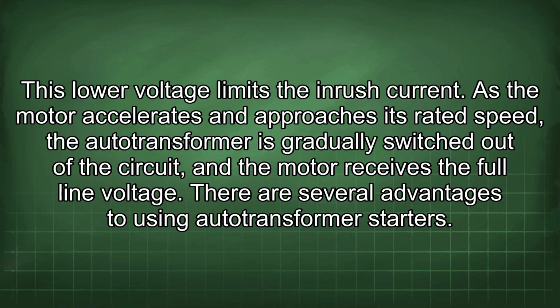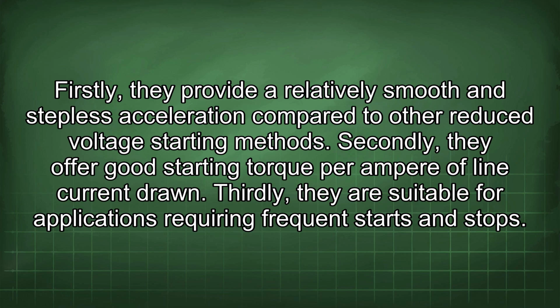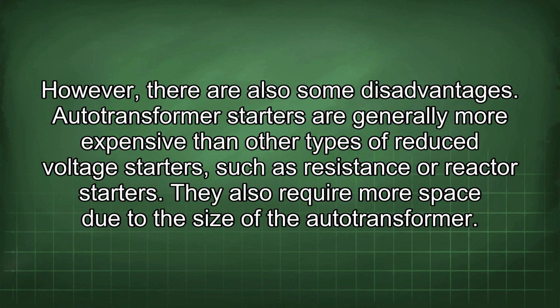There are several advantages to using autotransformer starters. Firstly, they provide a relatively smooth and stepless acceleration compared to other reduced voltage starting methods. Secondly, they offer good starting torque per ampere of line current drawn. Thirdly, they are suitable for applications requiring frequent starts and stops. However, there are also some disadvantages. Autotransformer starters are generally more expensive than other types of reduced voltage starters, such as resistance or reactor starters. They also require more space due to the size of the autotransformer.